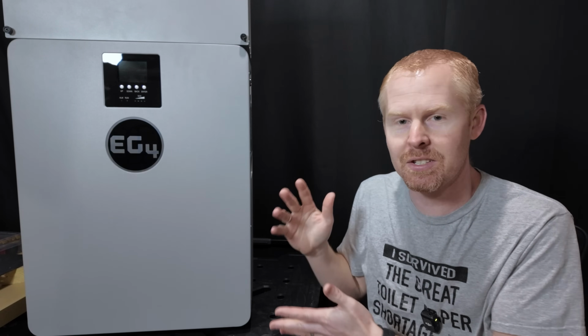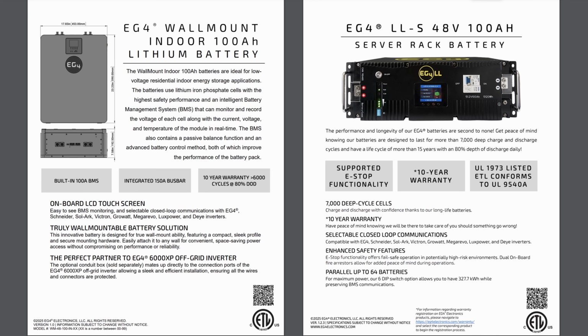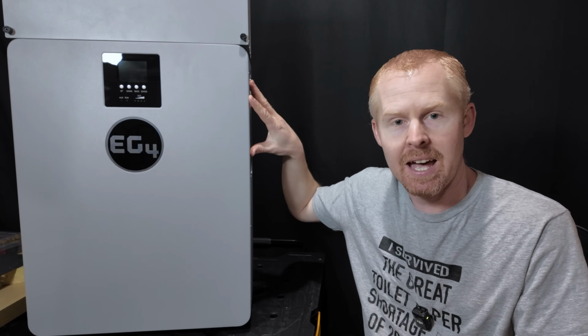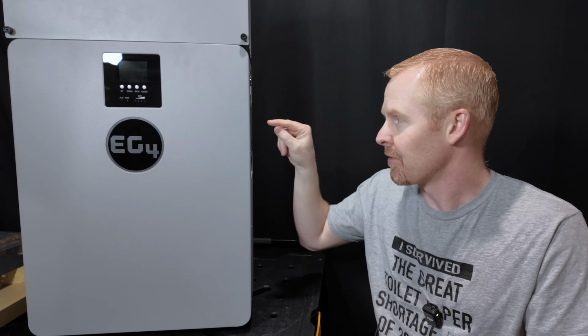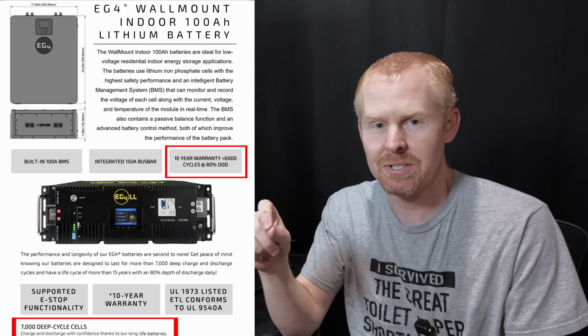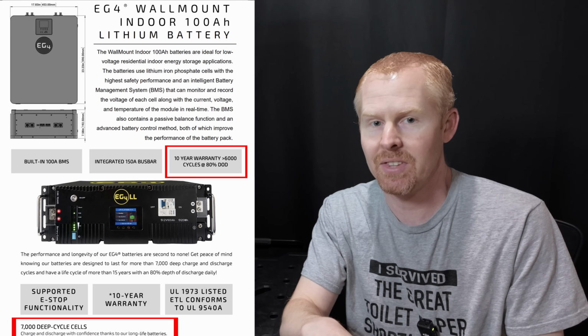When you compare this to the LL-S model, all the specs are virtually the same - same certifications, display, remote shutdown options, capacity, all those things are the same. The only differences I've seen, besides the obvious form factor, is this has the 150 amp bus bar built in, and the cycle rating for this is only 6,000 cycles versus the LL-S at 7,000 cycles. But that's really it, those are the only differences I can see between the two.